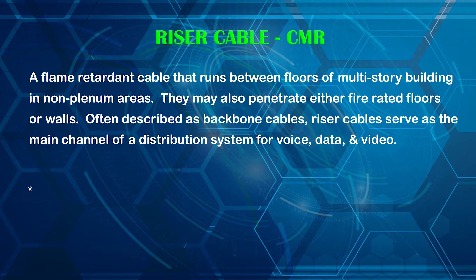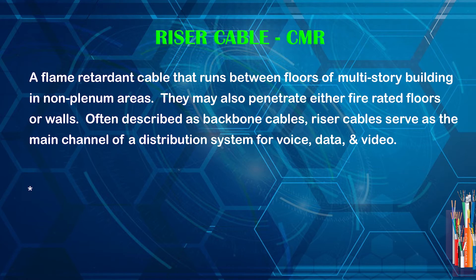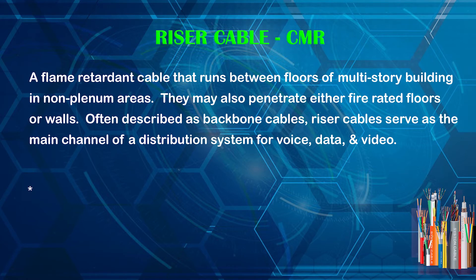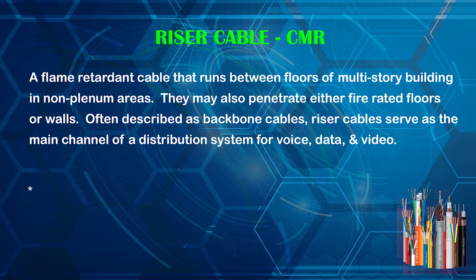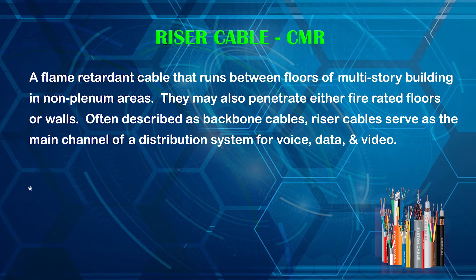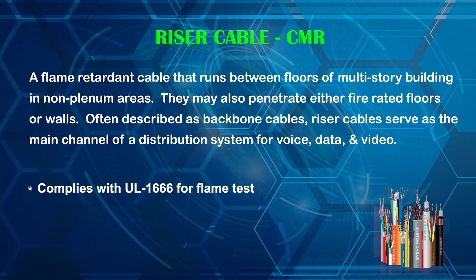Riser cables are flame retardant cables that run between floors of a multi-story building in non-plenum areas. They may also penetrate either fire rated floors or walls. Often described as backbone cables, riser cables serve as the main channel of the distribution system for voice, data, and video. Riser rated cables should comply with UL 1666 for flame testing.